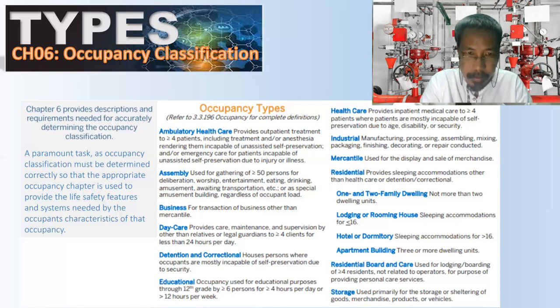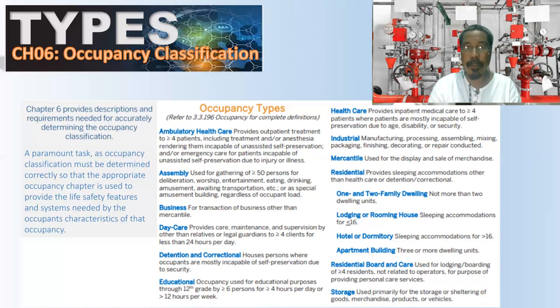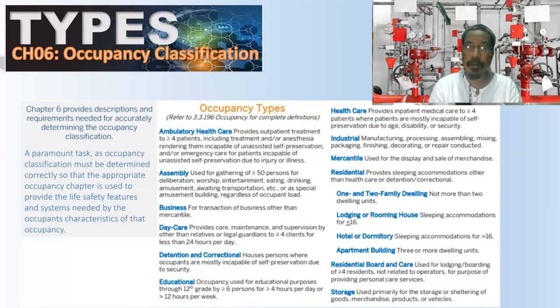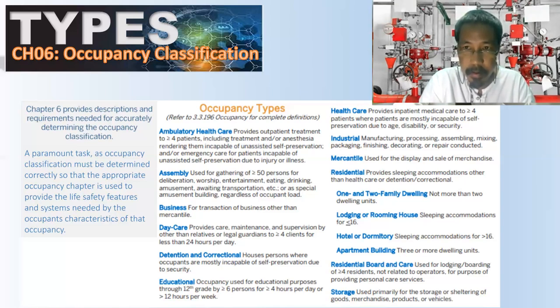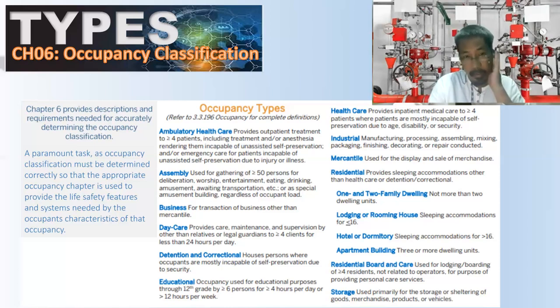Assembly occupancy is used for the gathering of 50 or more persons for deliberation, worship, entertainment, eating, drinking, amusement, awaiting transportation, or as a special amusement building regardless of occupant load. Examples include a church, where 50 or more persons gather, and a theater, where 50 or more persons are watching a movie — that is also an assembly occupancy.